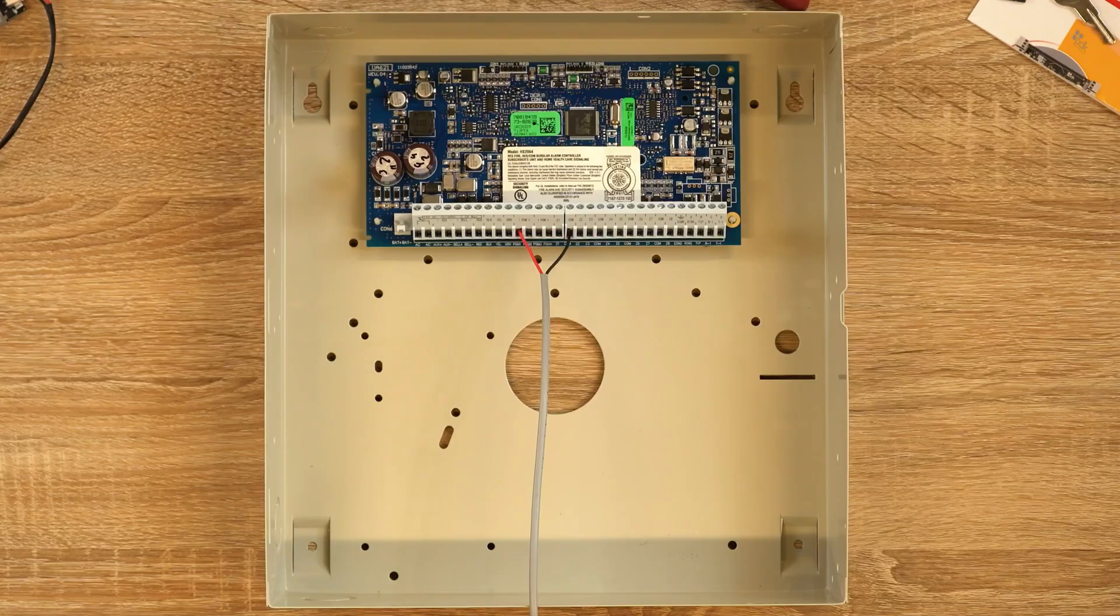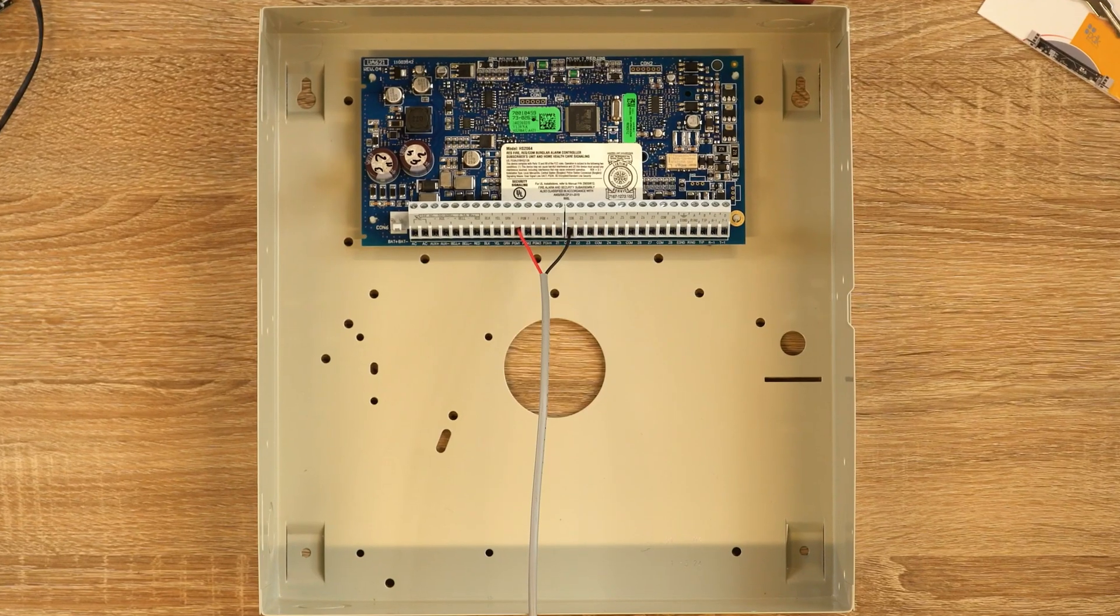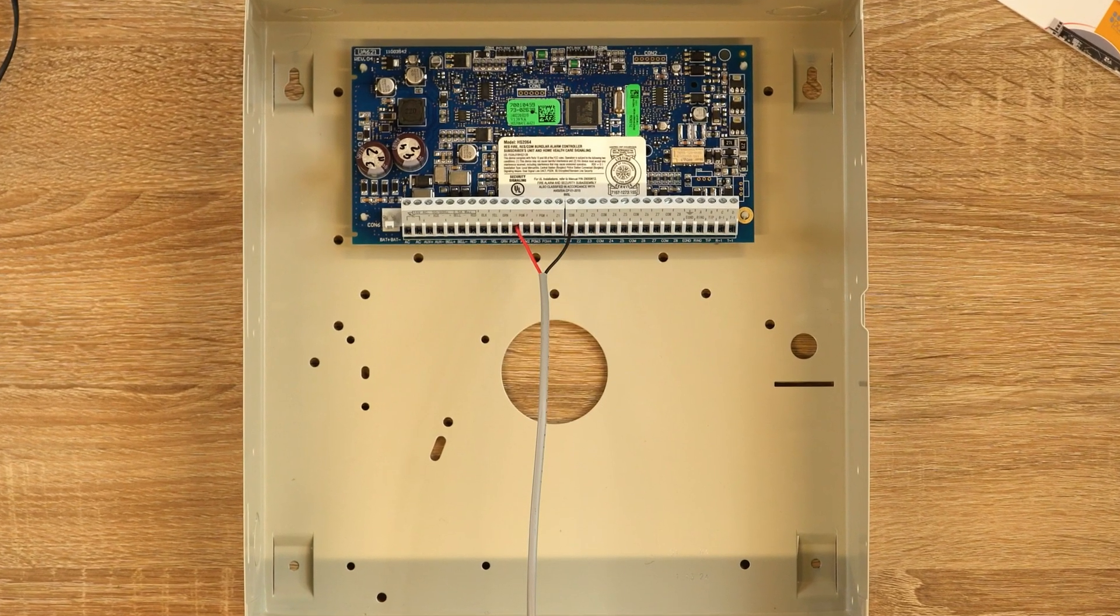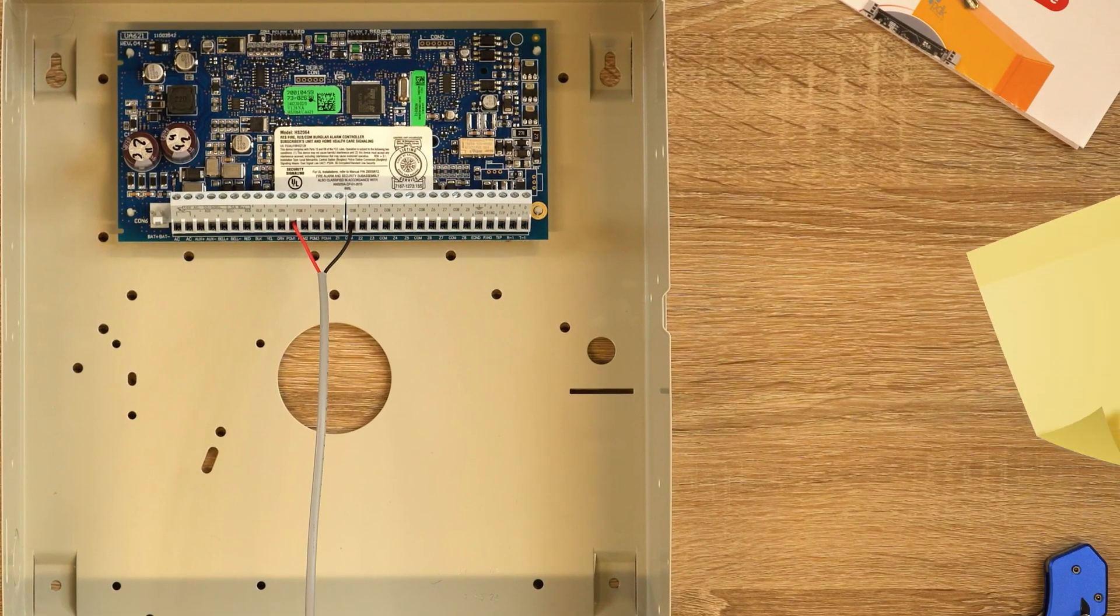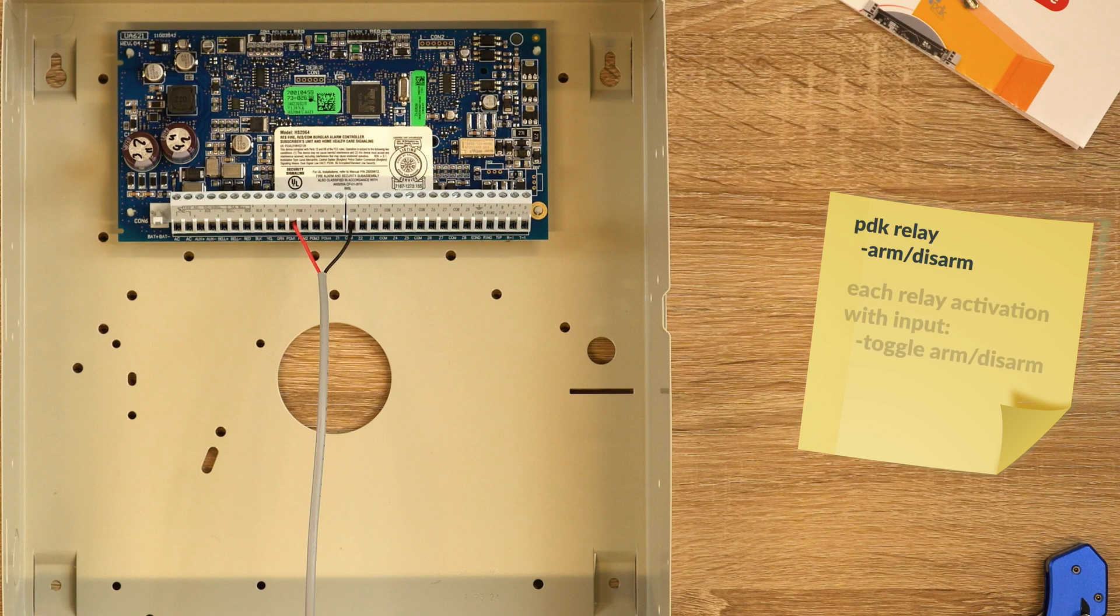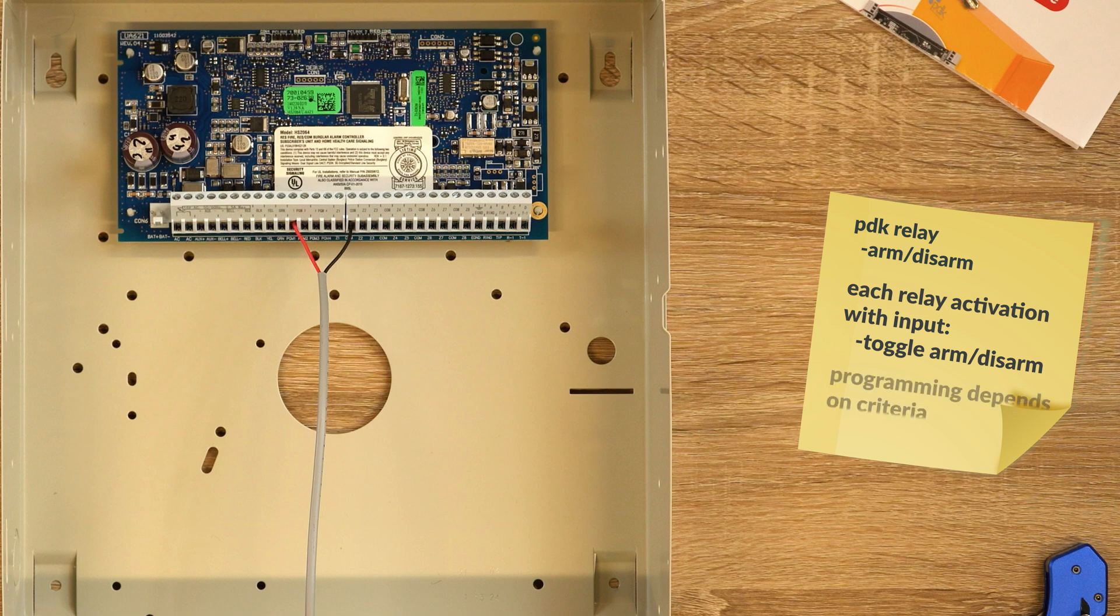Some alarm panels only have a single input labeled arm/disarm, in which case you will only need a single PDK relay to arm and disarm the alarm system. Keep in mind that each relay activation of this kind of input will toggle between armed and disarmed, so your programming will need to reflect for selective criteria.